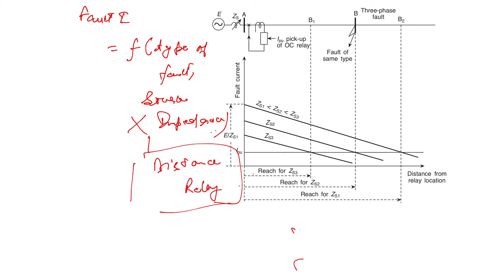Now we will discuss the introduction to distance protection. Let us consider the transmission line AB as shown in the figure, and let us assume that there is a source only at end A, that is, a singly fed system, and we wish to generate a zone of protection which extends from A to B. Now assume that the proposed relay is located at end A, where the current and the voltage are available through the CT and the PT, whose ratios we assume, for simplicity, to be 1:1. Now the reach of the distance relay is made equal to Z set.